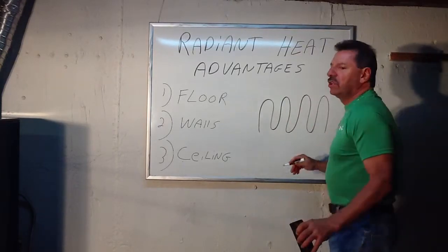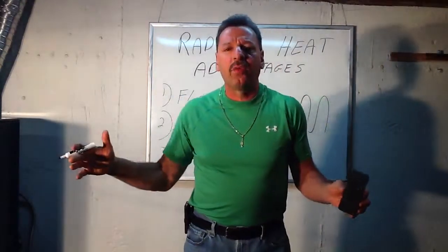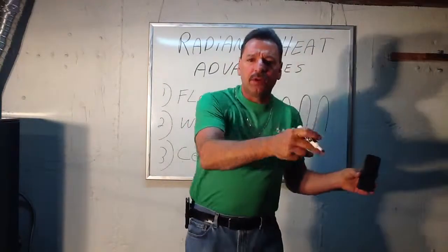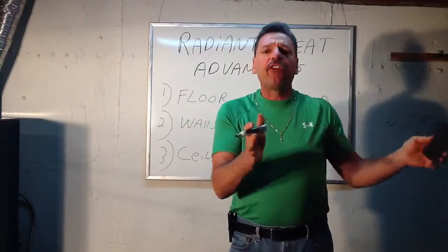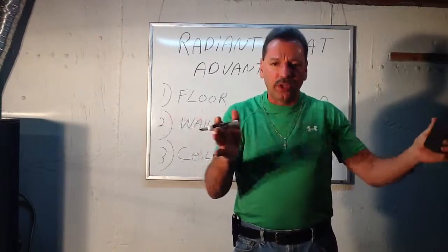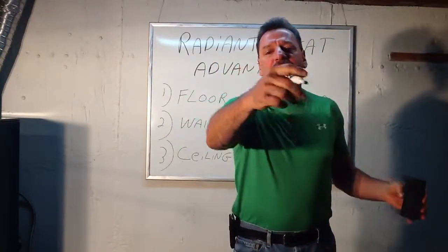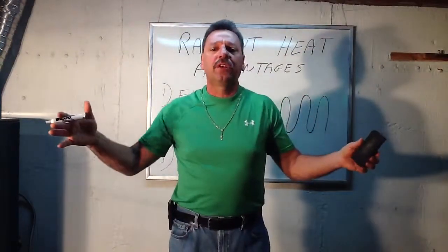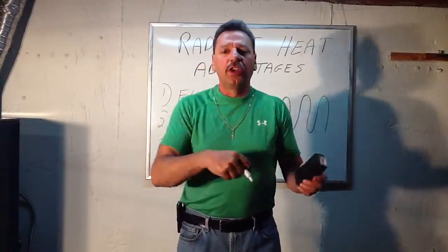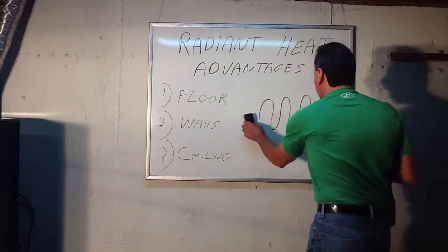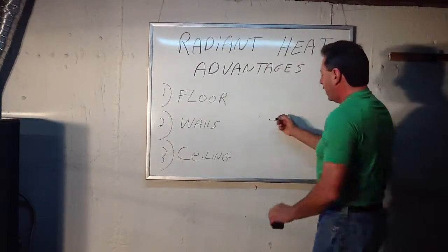And normally you'll do that if you have a cold outside wall. As you're doing the radiant along the floor, the first 3 foot going into the room, you'll squeeze those loops tighter, maybe 6 or 7 inches apart. And then as you get more than 3 foot into the room under the floor, you'll space the loops back a little wider to the normal 8 inches apart.